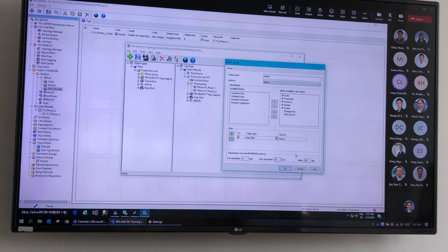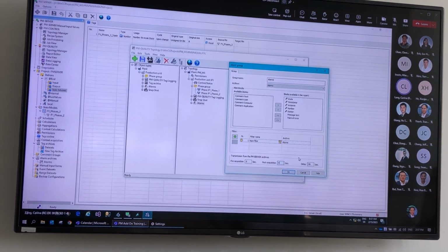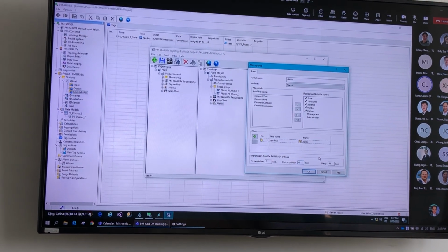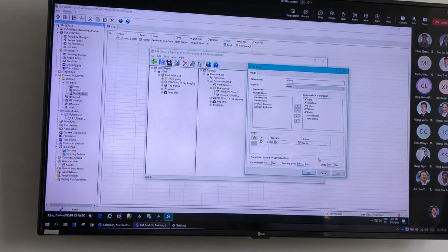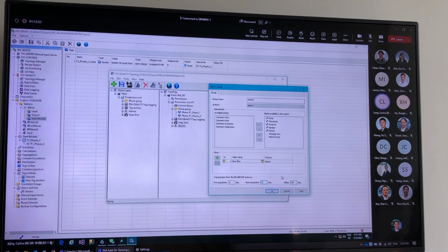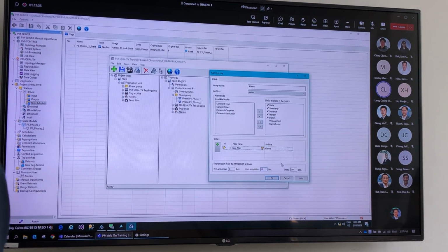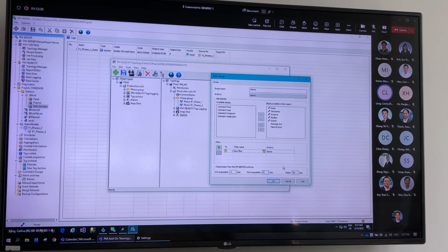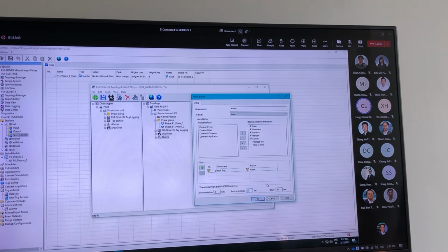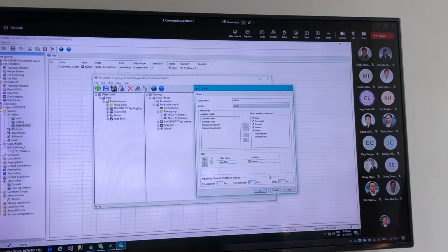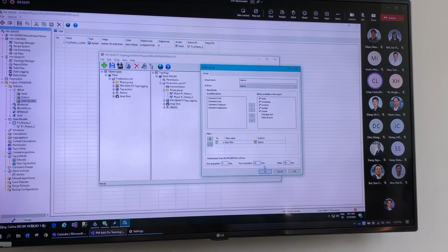Normally you do not have to change something here, but if you need some more alarms, because a short time before we start the batch we already create an alarm which is important to have inside of the report for this batch, then you can work with the pre-acquisition, for example, and the other way around. If we create some alarms after the batch is finished, but they are still important for this batch report, then you can use the post-acquisition so that we get some more alarms here. But normally you do not need that one, so we will skip this part here in the training project.